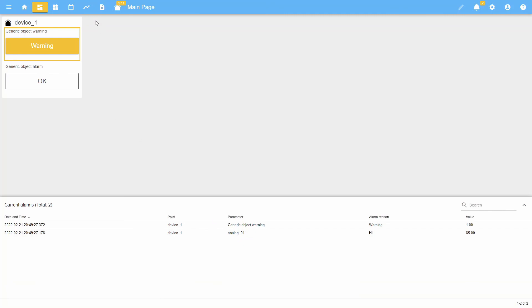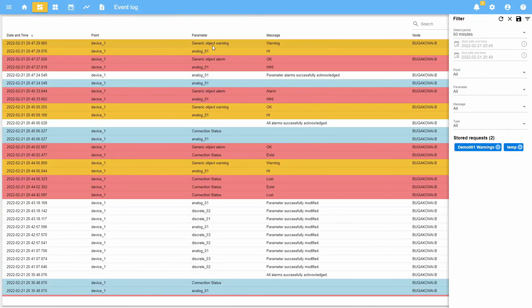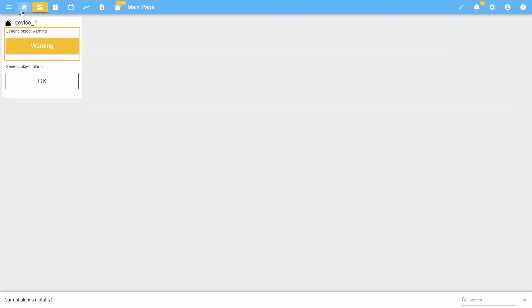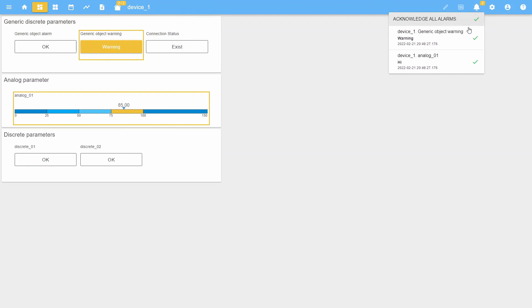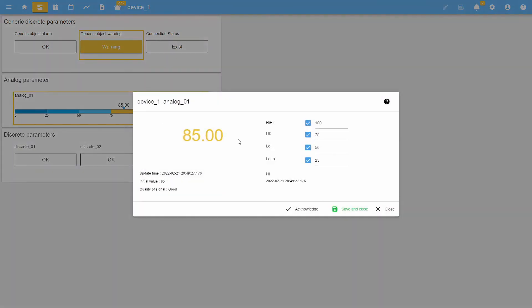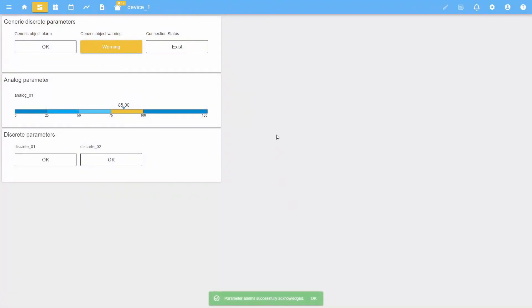All alarm and warning alerts are stored in the event log. There are three ways to acknowledge an alert: you can acknowledge alerts one by one using the alarm counter; you can acknowledge alerts one by one or all at once using the unacknowledged alarms button; or using the acknowledge button in the pop-up window when clicking on the widget. Thanks for your attention.